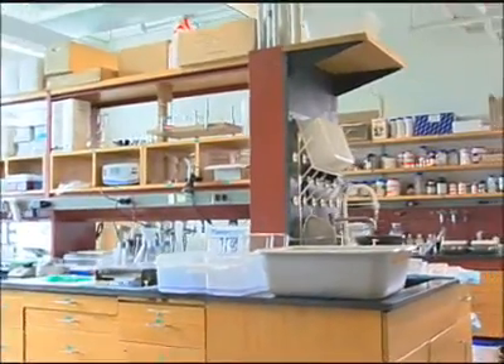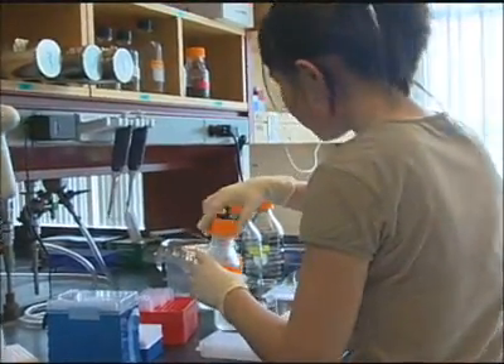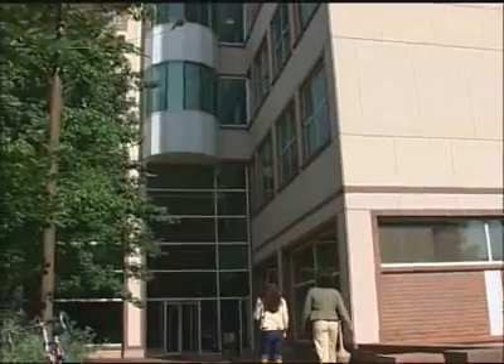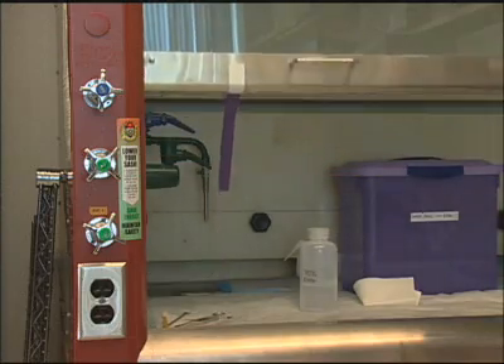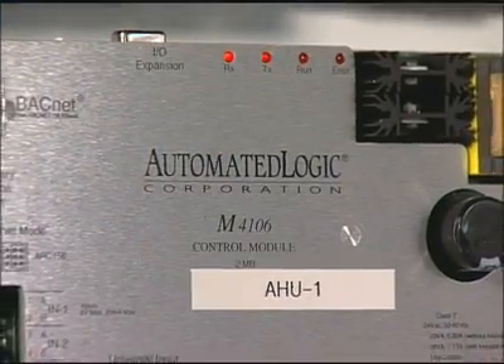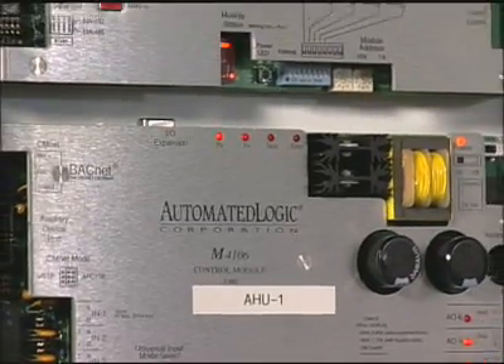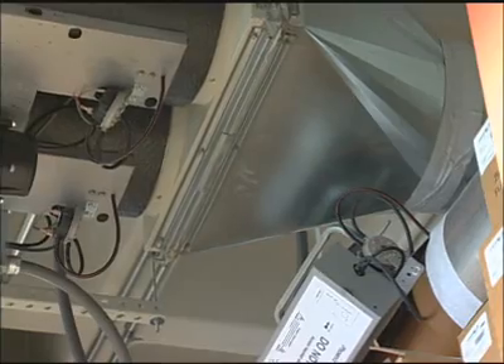The purpose for this project in the biotechnology laboratory spaces was to make the rooms more adaptive to the use going on in those spaces. Biotech was the largest ALC job that we've done to date. We took an existing large facility with a great deal of fume hood labs and retrofitted it with DDC, and also built in some intelligence as far as occupancy and ventilation rate changes based on occupancy.